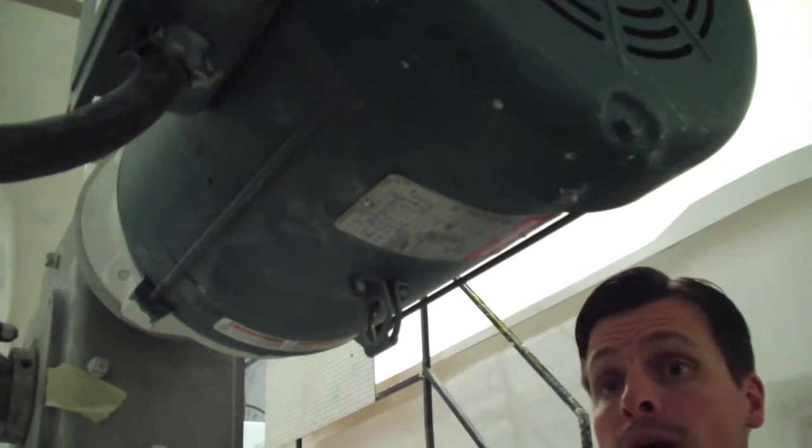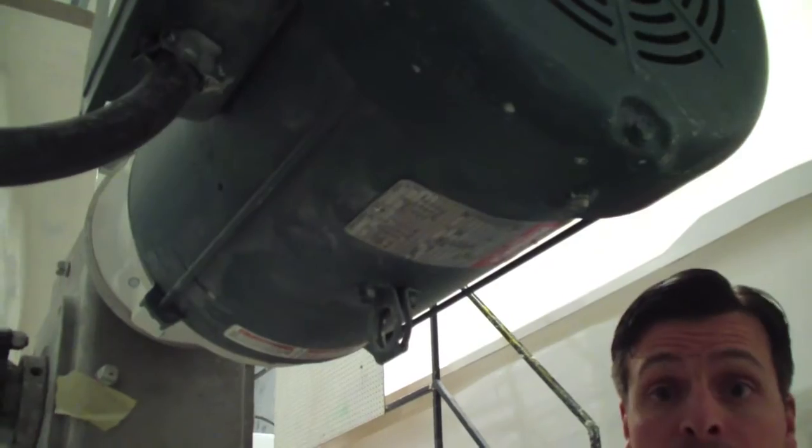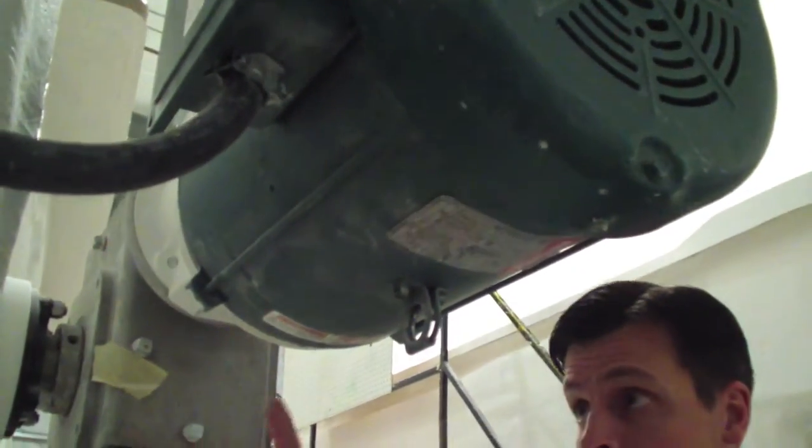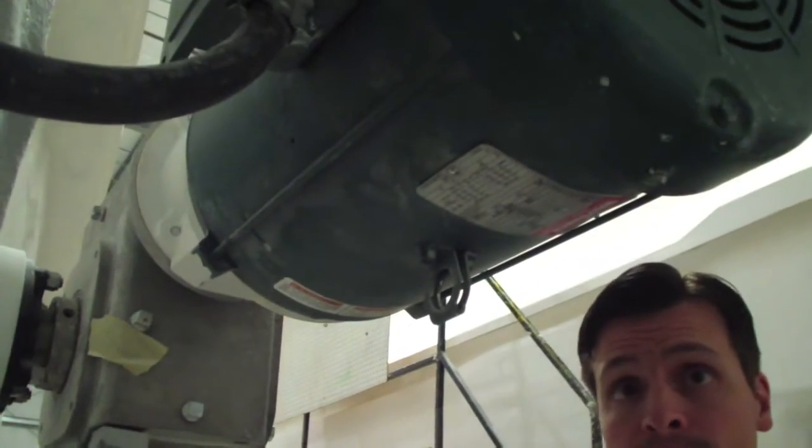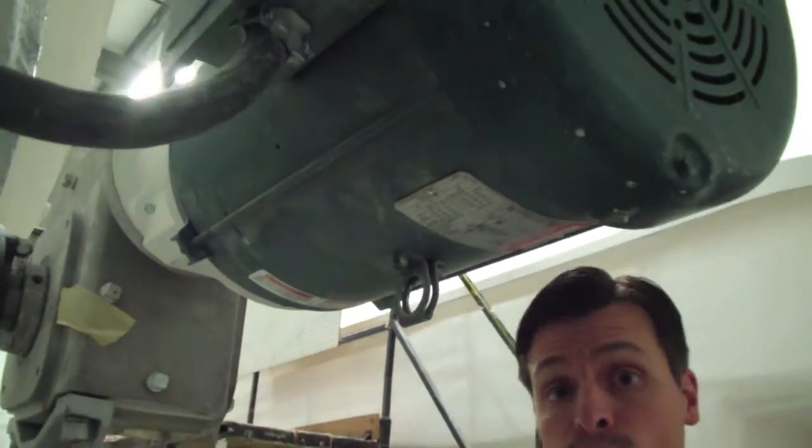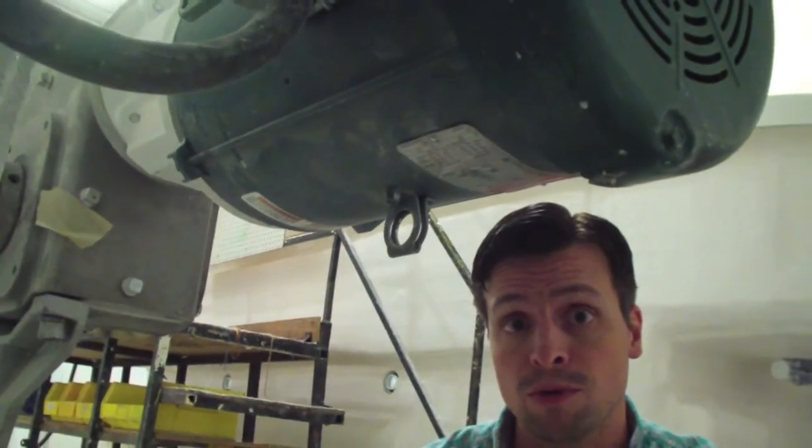Okay, so here we are. In this particular motor, the Zerk fittings are actually pointing downwards. So we have to go down and take a look at them. We have a standard Zerk here and one here. Same exact size, same exact premise. The only difference here is we want to give it four squirts of the general purpose lithium grease.